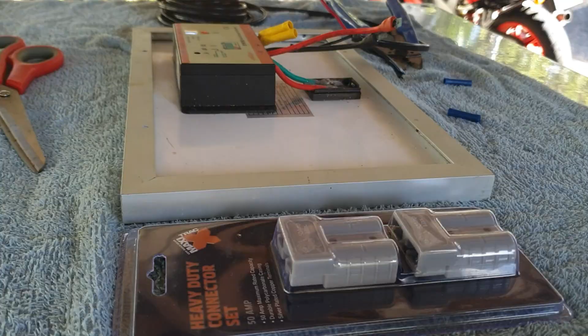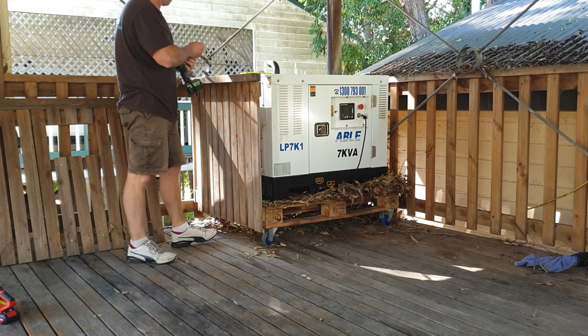Usually when we have a power outage, it takes 10 seconds for the switch box to switch over to the auxiliary power, being the generator, and then another 10 seconds for the sensor to tell the generator to turn on. So all in all, it takes 20 seconds to resume power back to the facility. On the reverse side, it only takes 10 seconds to revert back to mains power, so it's not left without power for long.